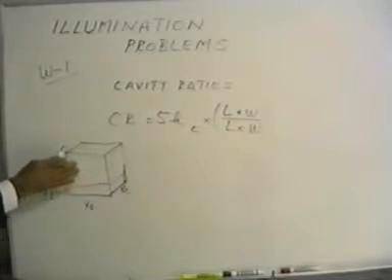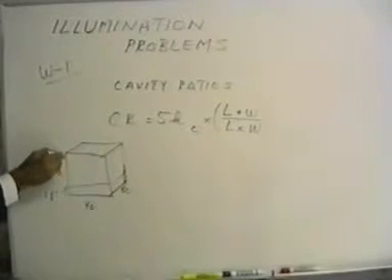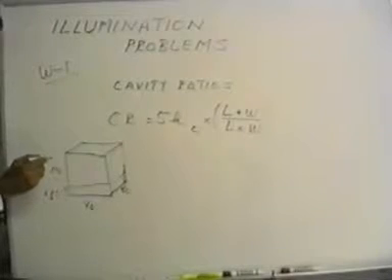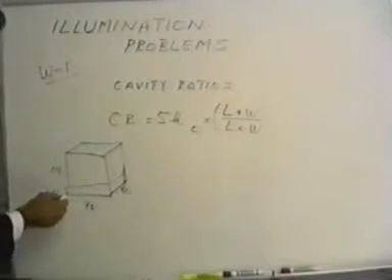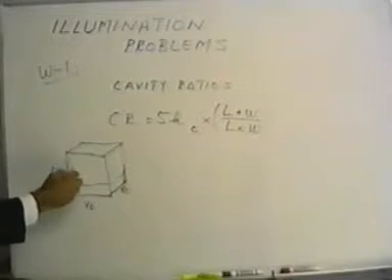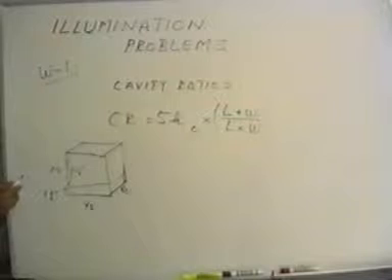In this particular problem, we're told the luminaires are right up against the ceiling. So if they're up here, there's virtually no dimension in here. There's no thickness to the ceiling cavity. So if this is 2.5 feet, then this distance in here would have to be 21.5 feet. And there's no ceiling cavity.